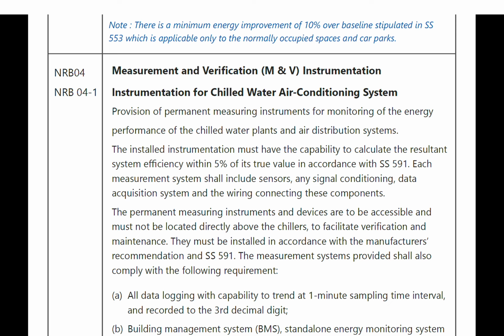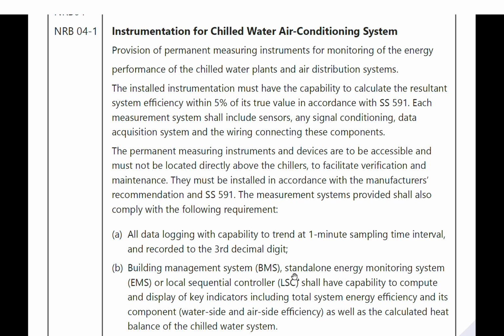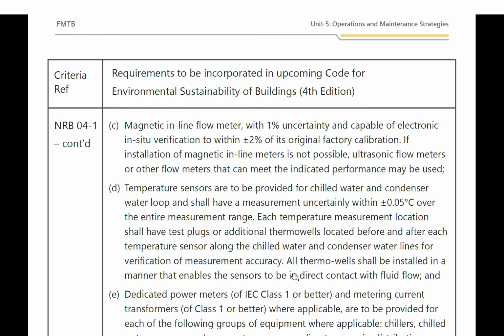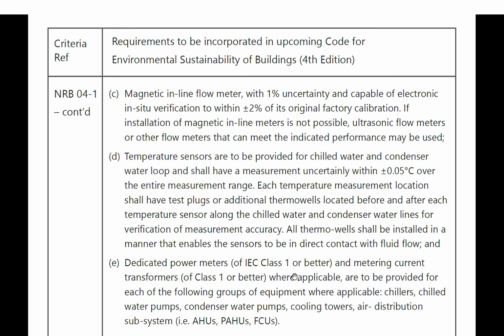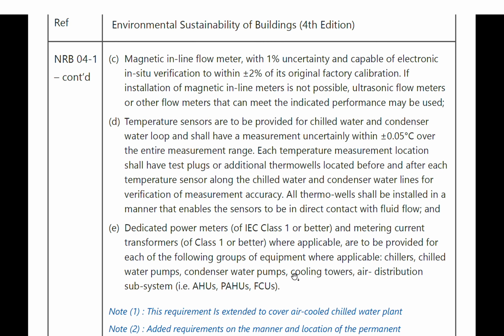The code is basically SS591, and once it's fulfilled, we use the BMS system to make sure that it's permanently measured so that we fulfill it, right. Data logging is about 1 minute per interval and up to 3 decimal places. The magnetic flow meter has a certain uncertainty, which should be about 1%, and in situ verification should be about 2% from the factory verification. The temperature sensor will have certain measurements, actually plus minus 0.05 degrees C for the entire measurement. A dedicated power meter should be there, measuring the power so that we can know the power for the various systems.